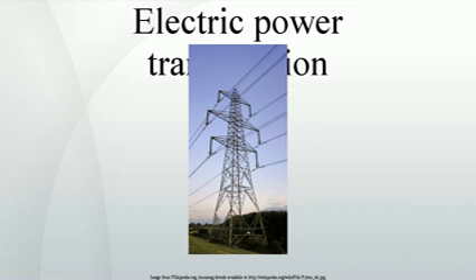Voltages above 230 kV are considered extra high voltage and require different designs compared to equipment used at lower voltages. Since overhead transmission wires depend on air for insulation, design of these lines requires minimum clearances to be observed to maintain safety. Adverse weather conditions of high wind and low temperatures can lead to power outages. Wind speeds as low as 23 knots, 43 km per hour, can permit conductors to encroach operating clearances, resulting in a flashover and loss of supply. Oscillatory motion of the physical line can be termed gallop or flutter depending on the frequency and amplitude of oscillation.